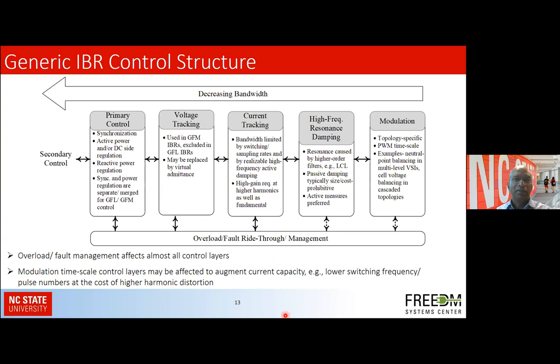So the generic IBR controller would have different levels, starting from the lowest level of modulation, which is essentially topology specific, and that's in the PWM time scale. And then there has to be the high frequency resonance damping for higher order filters like LCL filters. And that actually has an effect on the current controller bandwidth that can be achieved. So the next level would be current tracking, which is bandwidth limited, particularly due to these high frequency resonance damping requirements. The voltage tracking is not needed for the GFL converters, but needed for the GFM IBRs. And at the primary control layer would be the synchronization, the active power and the DC side regulation, and the reactive power regulation. The synchronization and power regulation are separate for the GFL converters, but they are actually merged for GFM converters.